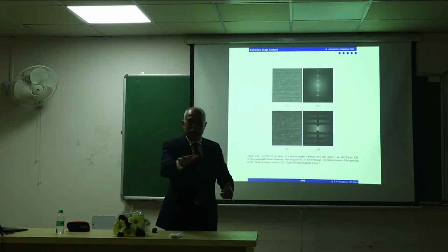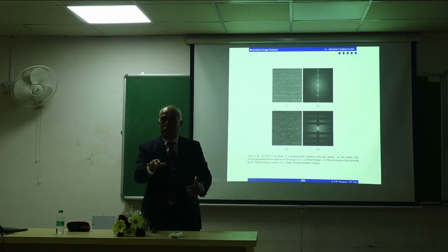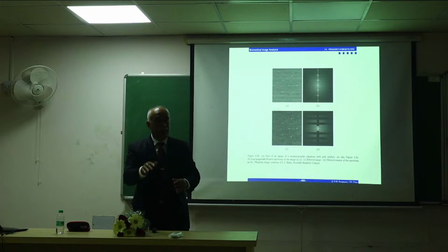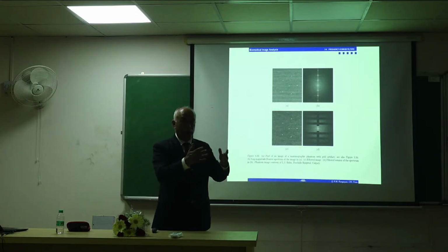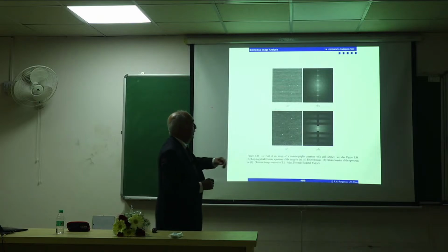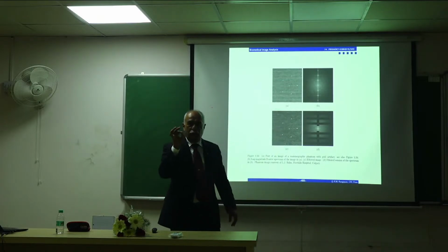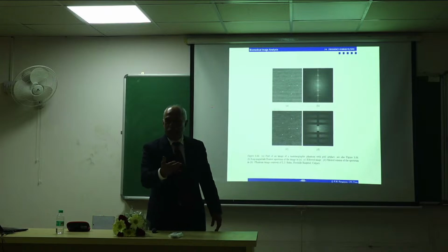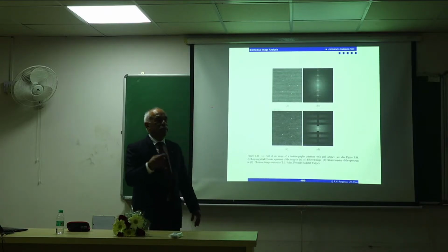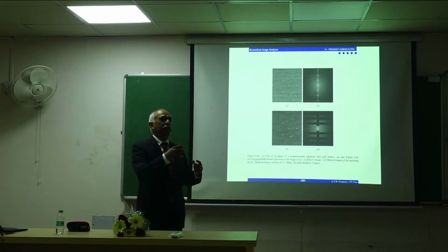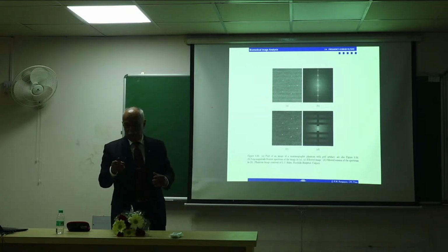And there could be some grids there, and you want to make sure that the high frequency grids will still be visible with good resolution in the image that you acquire. And calcifications such as these fine spots should be clearly visible. You measure the contrast and so on. So for each body system or part and each imaging system, there are various phantoms.